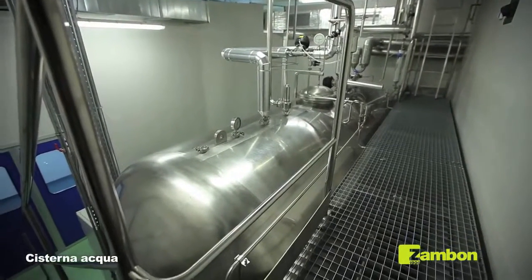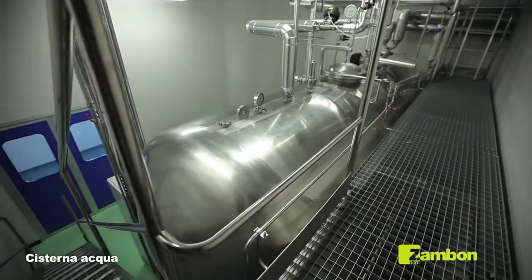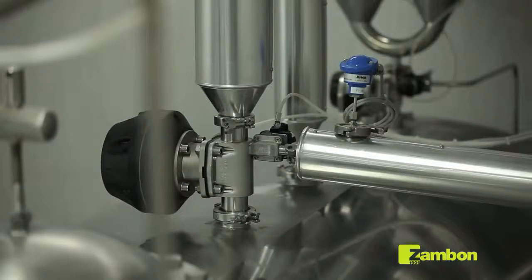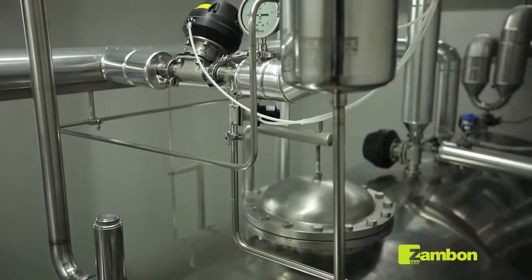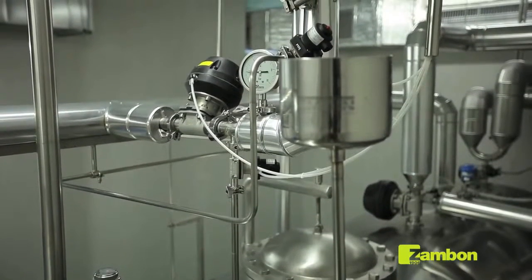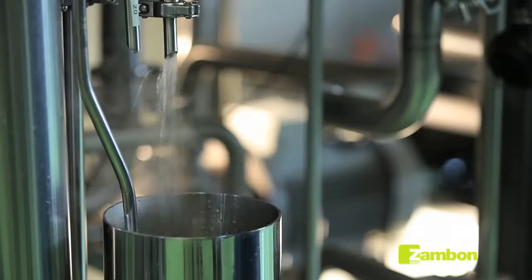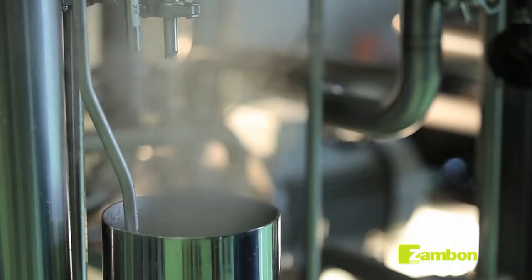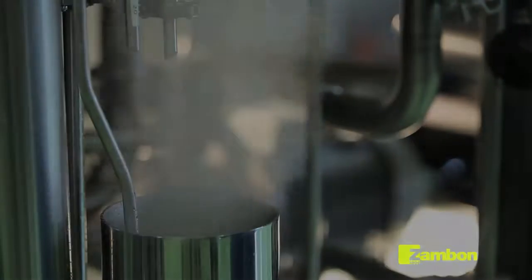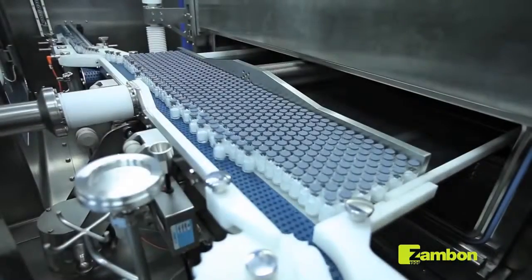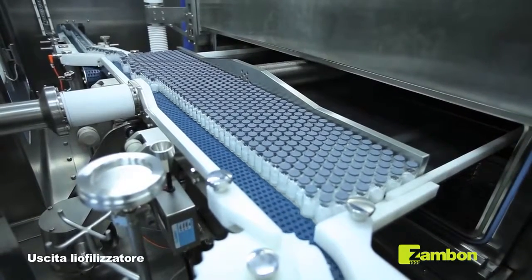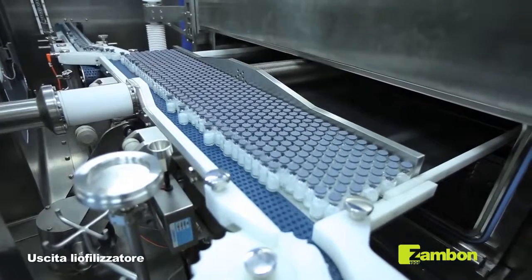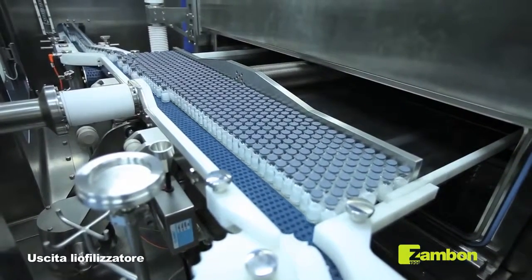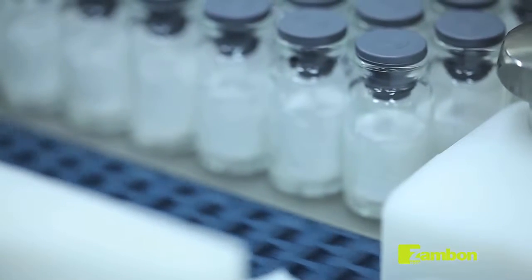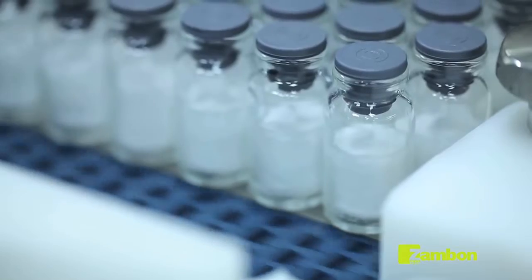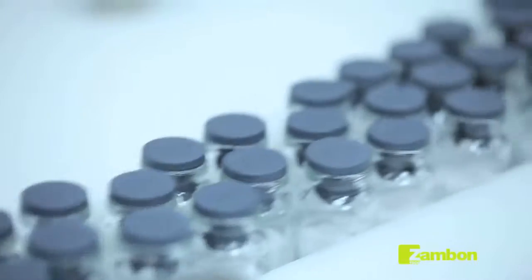A 15-meter cube stainless steel tank collects the water for the injectables required for production of the lyophilizates. The water is then maintained at a temperature of 85 degrees Celsius and recirculated continuously in order to avoid the growth of microorganisms. Lastly, the water is monitored continuously and analyzed chemically and biologically. The lyophilization cycle may typically last from 24 to 48 hours. At the end of the lyophilization, the bottles contain the characteristic lyophilized powder inside the bottle.